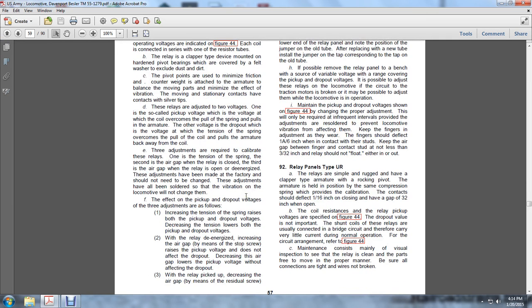Relay panels of the type UR. The relays are simple and rugged and have the clapper type armature with a rocking pivot. The armature is held in position by a compression spring which provides the calibration. Contacts should deflect 1/16 of an inch on closing, having a 1/32 inch gap when open. Coil resistance and relay pickup voltages are specified on figure 44. The dropout value is not important.